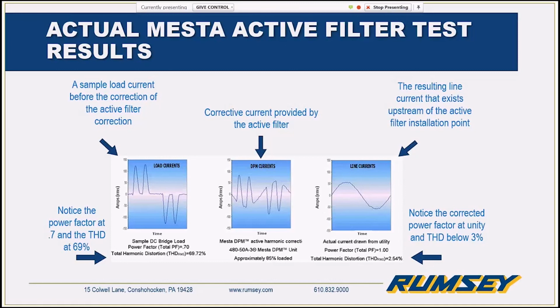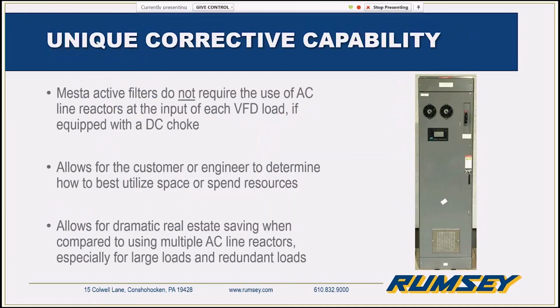There's a very unique advantage for that corrective capability you saw on the last slide: we are the only active filter that does not require the use of line reactors if the drive has a DC choke. So this is why we work very well with ROCKWELL and their PowerFlex 750 series drives, because with that DC choke that they have, it allows the designer to say, what do I have room for? Because line reactors are very good for the VFDs.